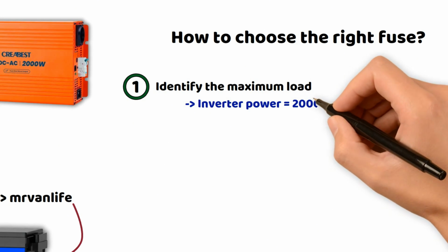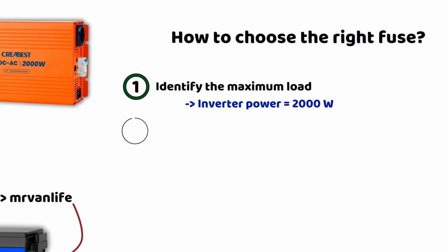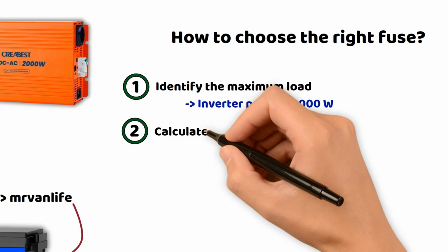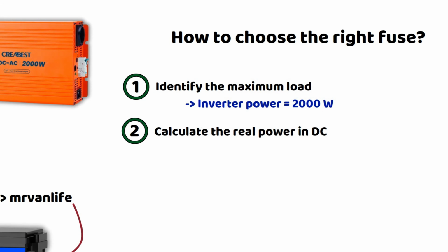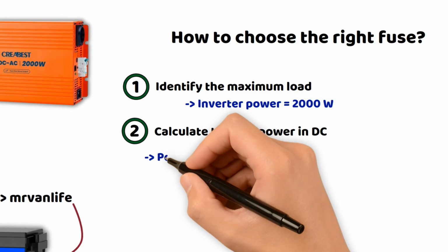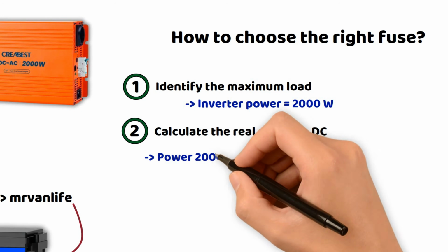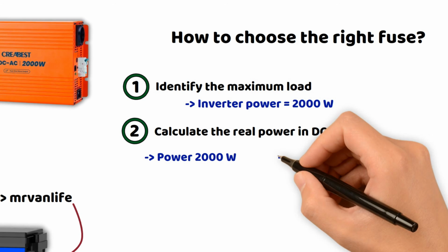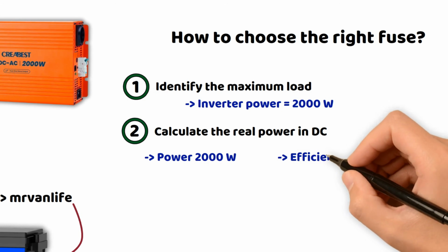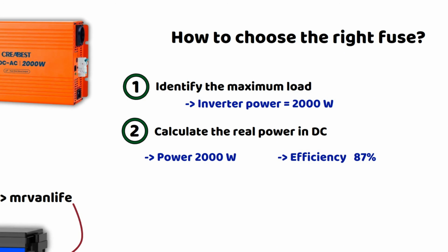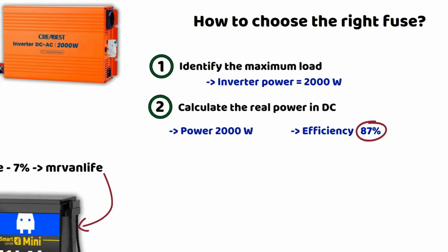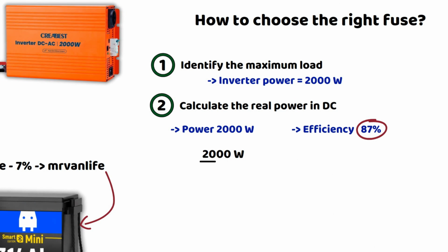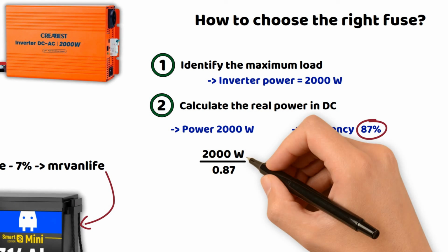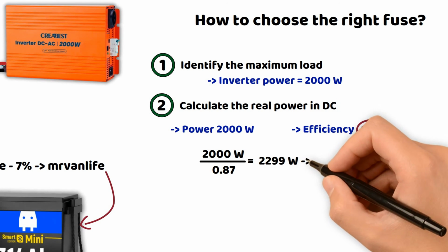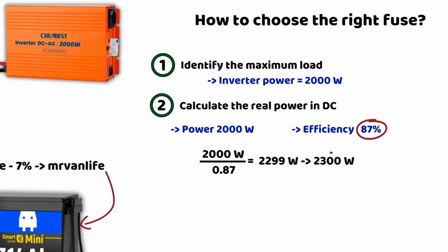Step 2. Calculate the actual power in direct current. It's important to understand here that the inverter can power a 2000-watt device, but it also has its own consumption due to energy loss when converting 12 volts to alternating current. Here, the Creabest inverter has a minimum efficiency of 87%. So here, we'll take the worst-case scenario and do a simple calculation. 2000 watts divided by 0.87 equals 2299 watts, so we'll say 2300 to round it off. That's the actual power the battery needs to supply.